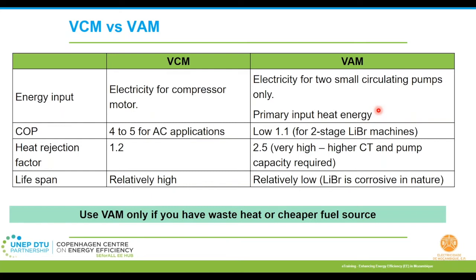Electricity is required, but only in very small amounts to operate the circulating pumps within the equipment. So you do not have to consume a lot of electricity here, but you will need another form of energy, that is heat energy. With respect to efficiency, vapor compression machines are quite efficient, with a COP of about 4 to 5. The VAM machines are again slightly inefficient. The heat rejection factors for VAM machines are on the higher side. That means to reject the heat being absorbed, you will require a much higher capacity cooling tower or pump circulation capacity.